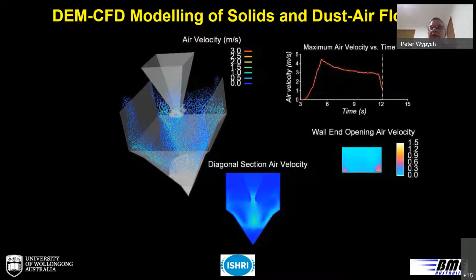So we had to rely on modeling, which we did here. Again, we used the coupled DEM-CFD approach to give us the energy level, so we knew what sort of energy we needed from the micro-mist system, from the nozzles. You can see the peak air velocities in the corners, so we put some extra nozzles in there to counter that energy.